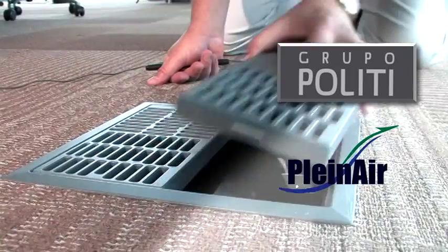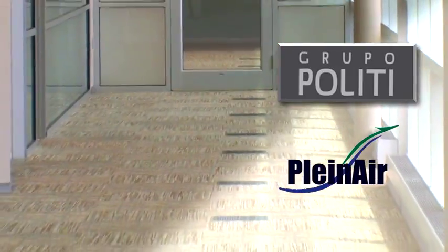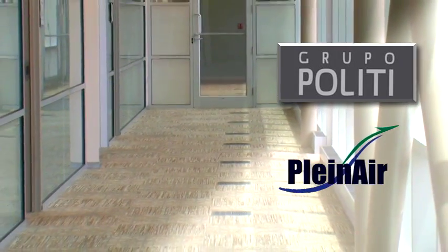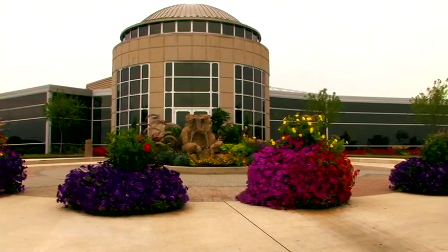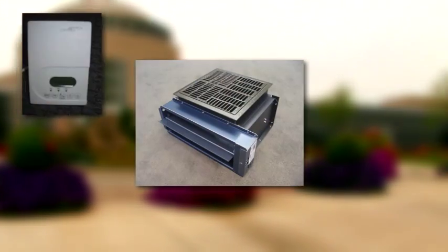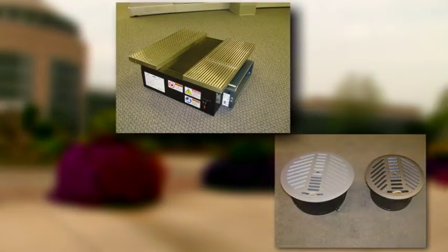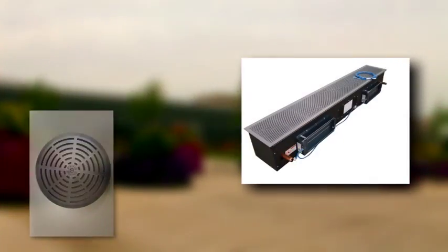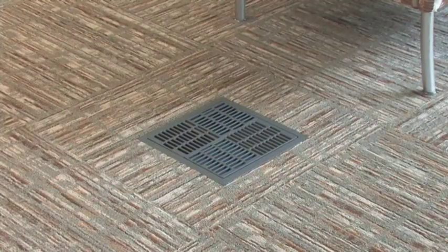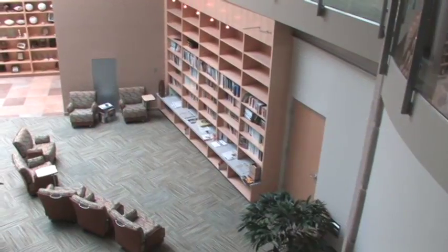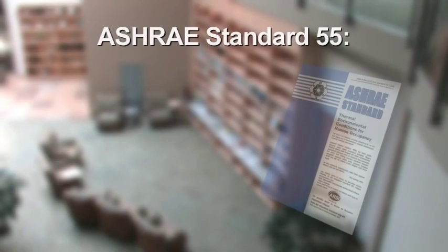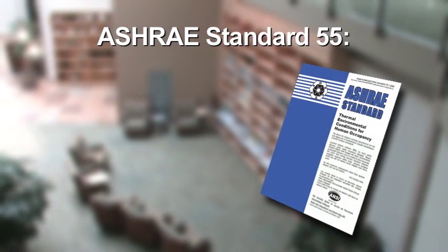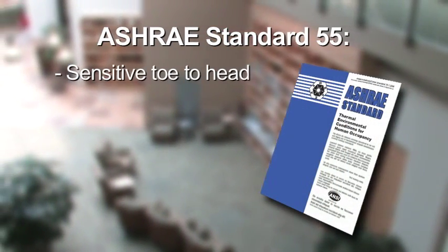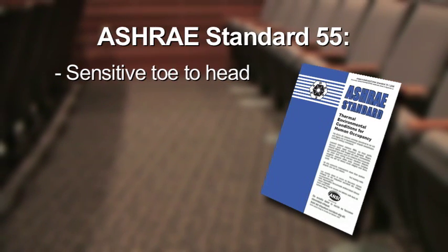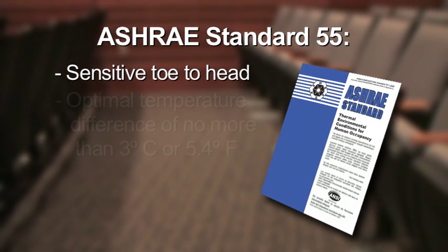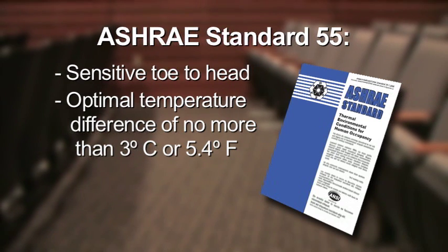The PleinAir brand underfloor air distribution systems and the associated controls are among the most innovative technologies on the market today. These air systems help owners secure their LEED ratings while providing superior occupant comfort. Thermal comfort, as provided in modern buildings, is defined in ASHRAE Standard 55. The standard states that humans are sensitive to rising temperatures from toe to head and recommends an optimal difference of no more than 3 degrees Celsius.